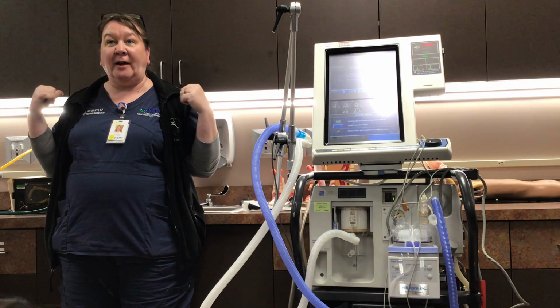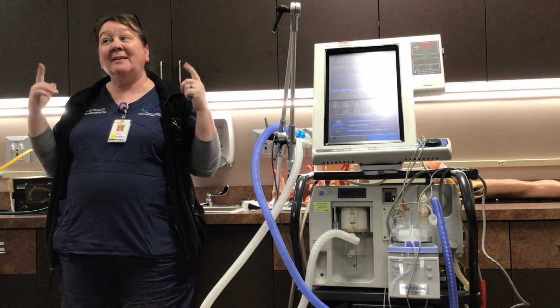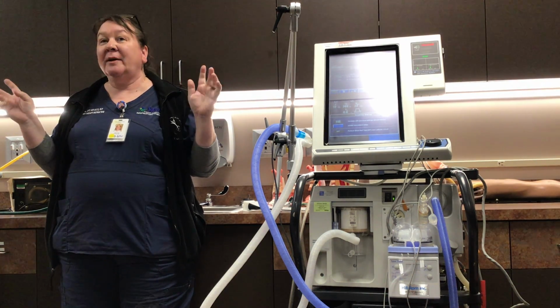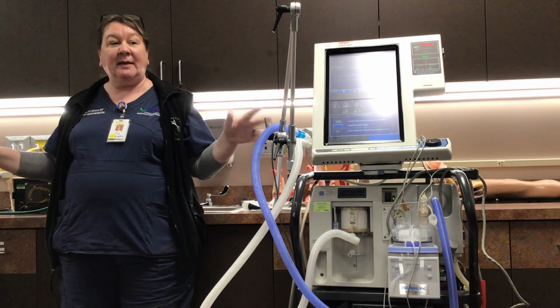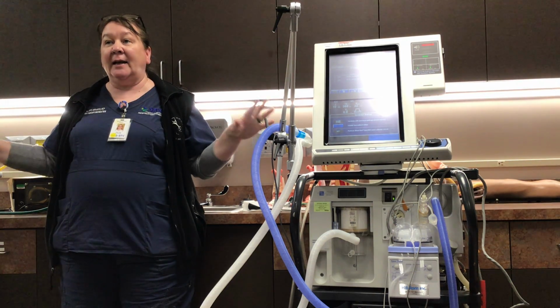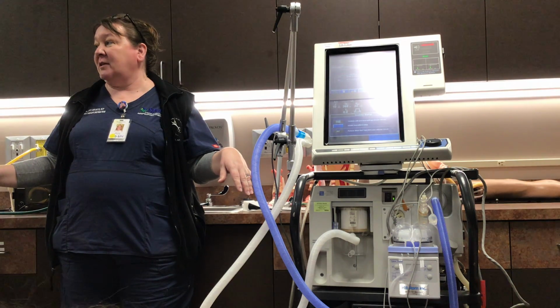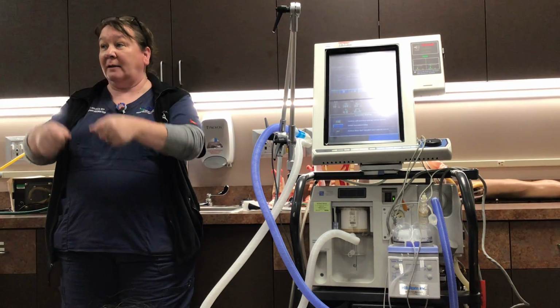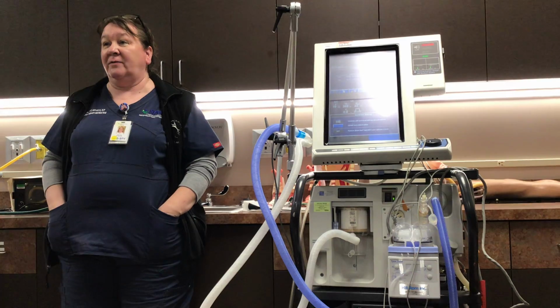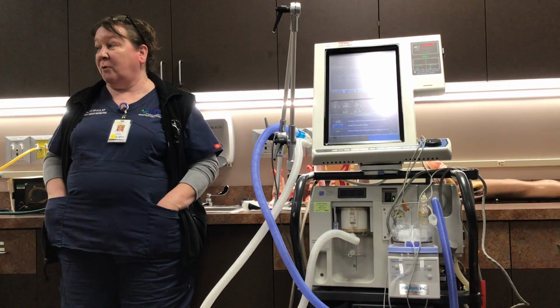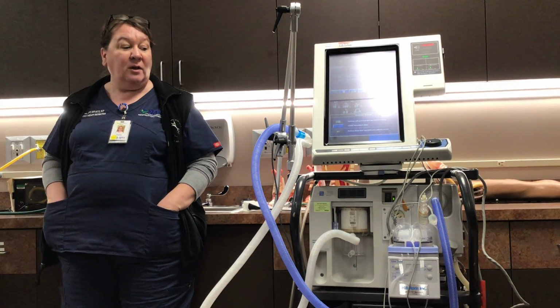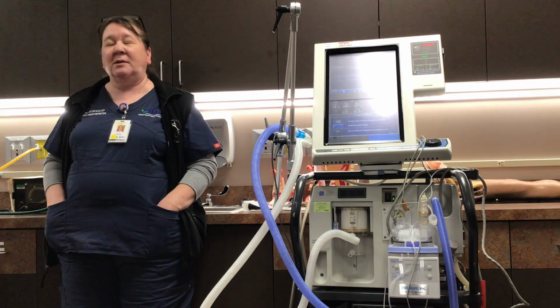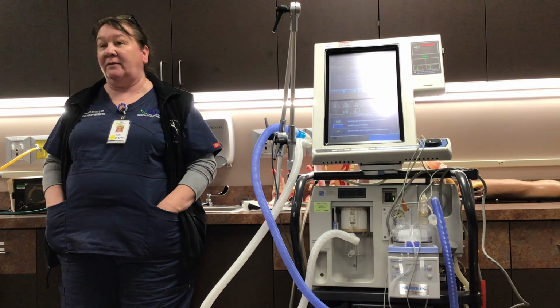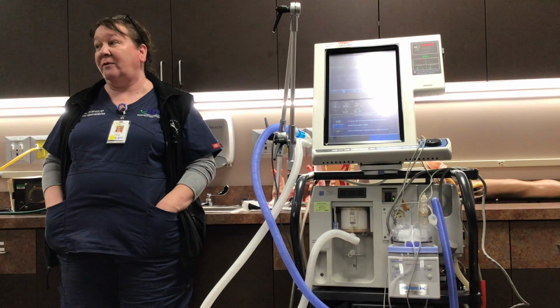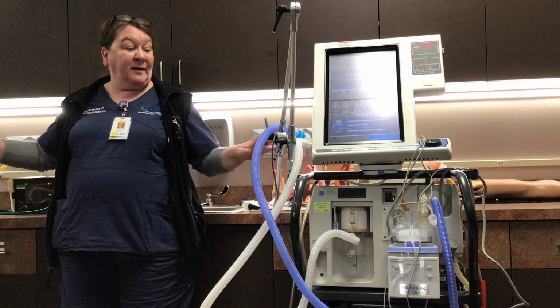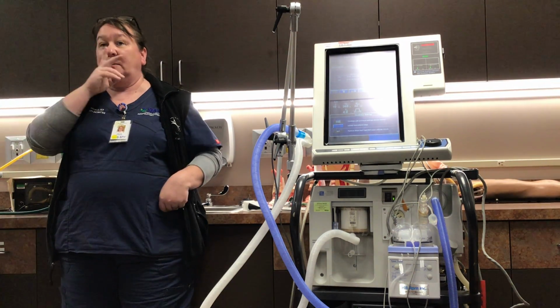But what if the generator fails? And that has happened as well. So the generator fails, you got probably like 5 or 10 minutes to get in here and get the patient on some alternative source, which would be bagging them until the situation gets fixed. That has happened at hospitals before as well, where the generator has failed. So know that your internal battery does not last very long. It might say an hour in the manufacturer's guidelines, but they do not. You're trying to power this big machine here.